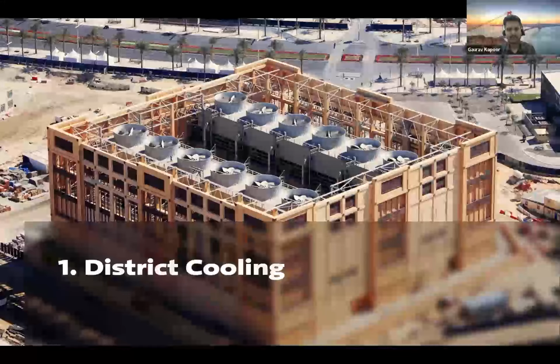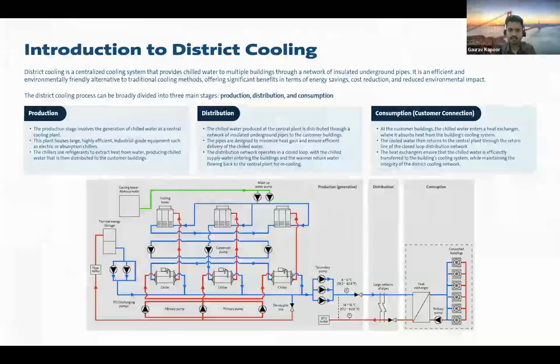Now, district cooling, just to touch base, is a centralized large-size HVAC cooling plant where the production happens with the help of chillers. The chilled water is distributed with the help of pipes laid out in the ground and consumed by the end customers. It can be an industry, a residential building, a hospital, or a mixed-use building, with the help of an energy transfer station, which is just a heat exchanger and a set of pumps, or directly connected to the buildings.